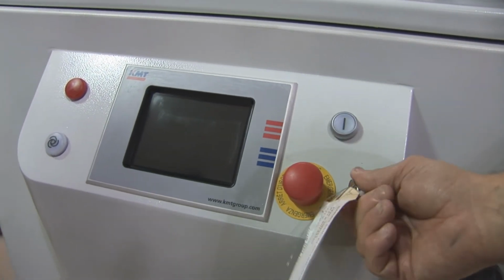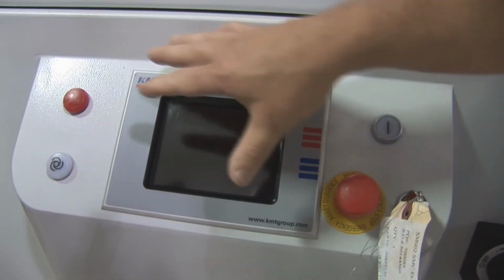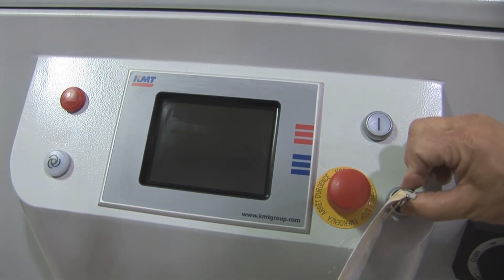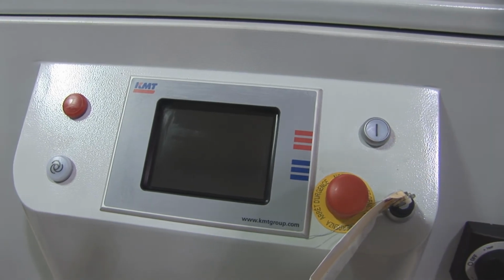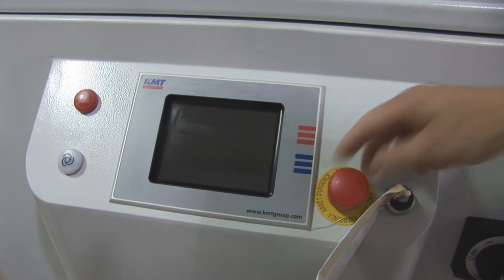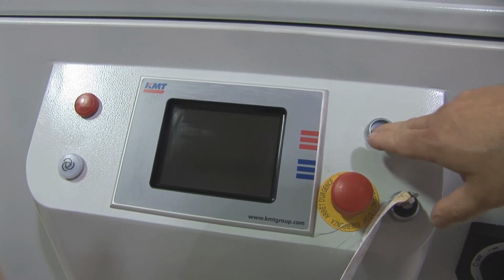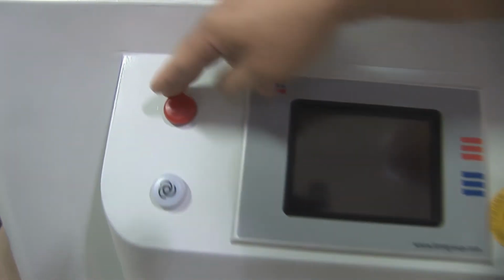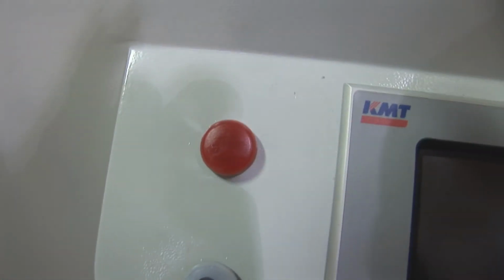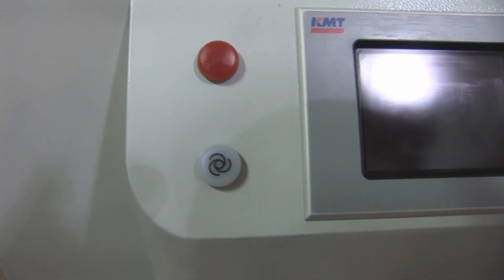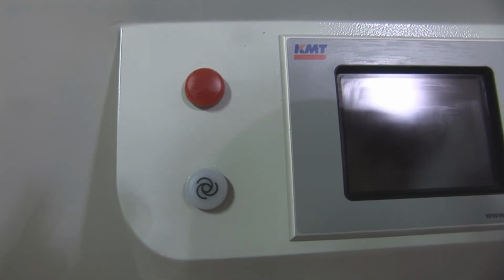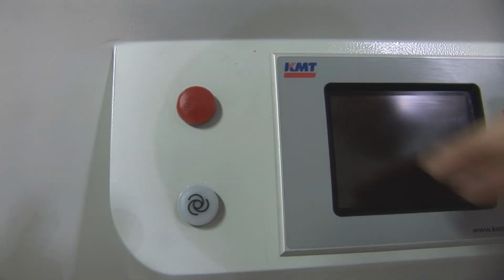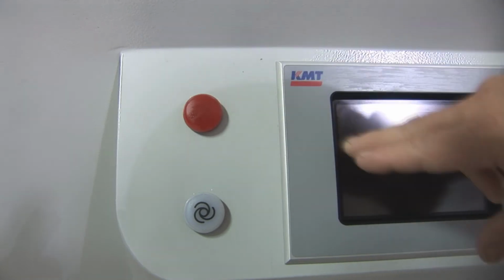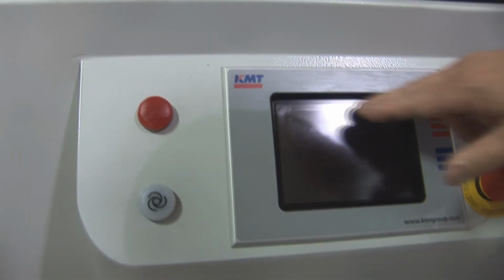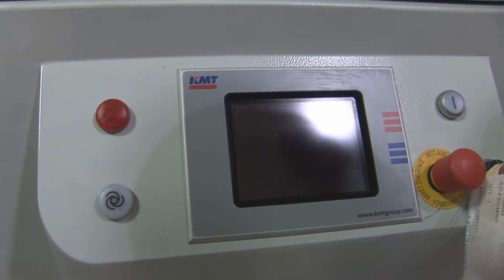When the key is to the left, it means you can start and control the pump from this panel. When the key is to the right, that means your remote control is taking over. You pull the EStop out, hit your reset button, and then you have a warning light. If you do have a problem, your red light will come on and flash. This is the pump running light. If everything is normal, that light will be on. Anytime the machine shuts down for any fault, when the light comes on solid, your display will give you a menu to choose from to let you know where the problem could be.